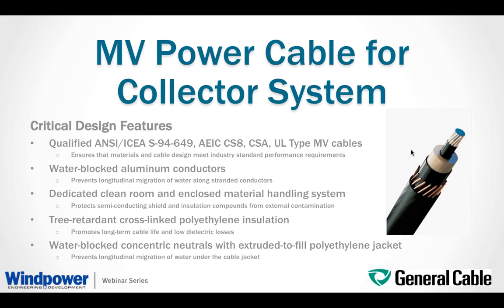And then the use of water block stranded conductor, with a conductor size ranging from 1 up to 1250 kcmil, would prevent longitudinal water penetration along the length of the stranded conductor and extend cable life. The benefit of using water block conductor has been demonstrated using ACLT, accelerated cable life testing. And then on the material, clean materials, dedicated clean rooms, and an enclosed material handling system ensure protection of the semiconducting shield and insulation compounds from external contamination.